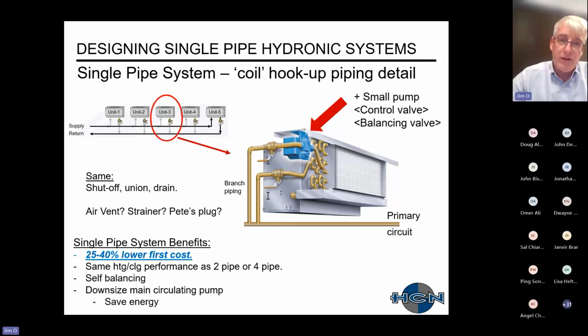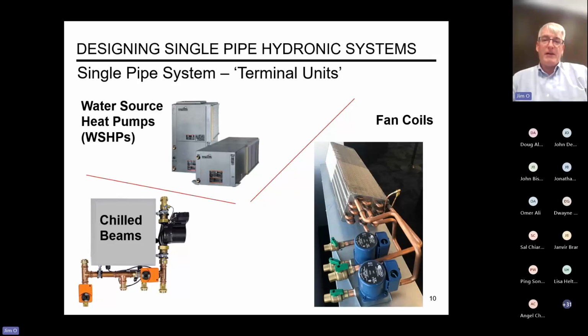And then with single pipe hydronic systems, the main benefit of this type of system is that because you have less piping mains, you'll save a lot on your lower first cost. You'll end up with the same heating or cooling performance as a two-pipe system, so you don't have to worry about comfort. These are self-balancing, and I'll show you in a couple slides, but you're able to downsize your main circulating pump, and that will result in energy savings. These single pipe hydronic systems are primarily used for what I'll call terminal units. A couple of systems or equipment are depicted here: water source heat pumps, chill beams, as well as fan coil units.